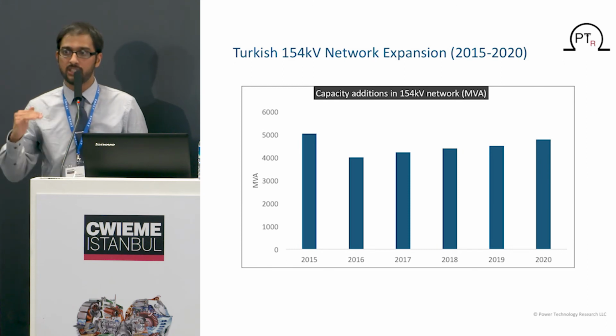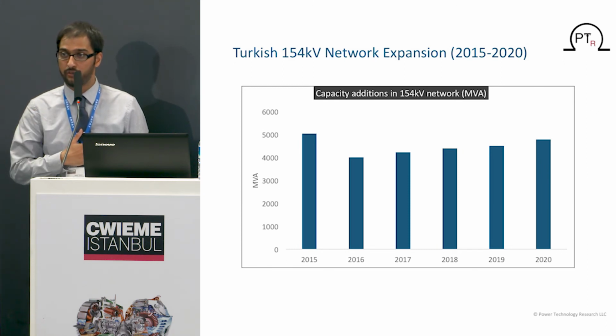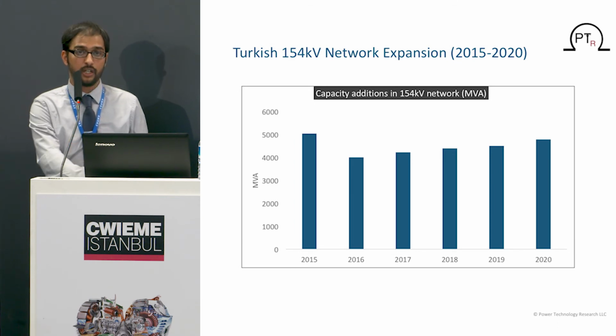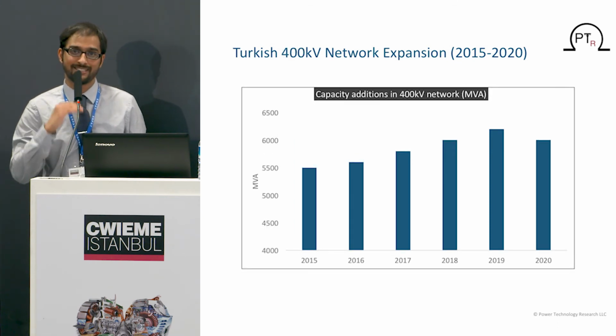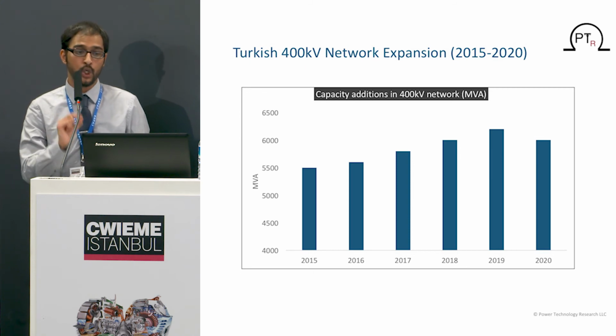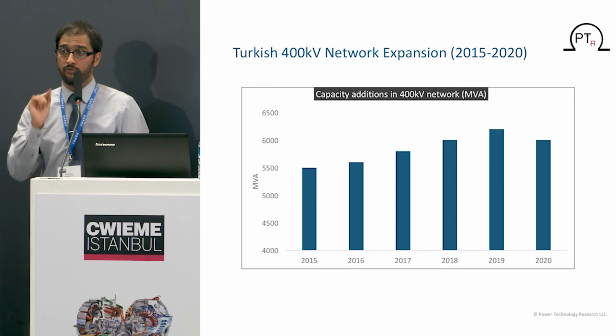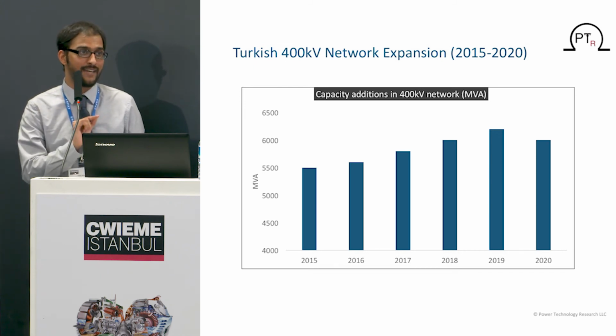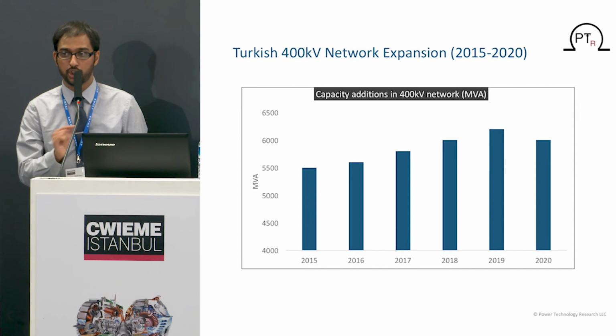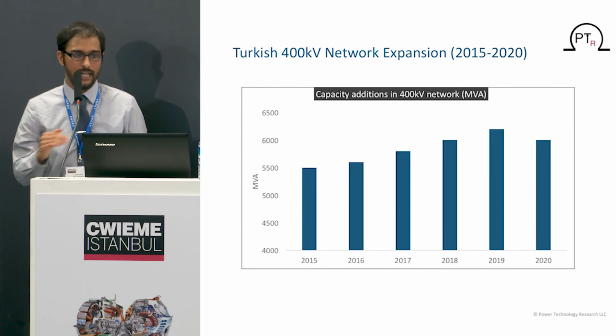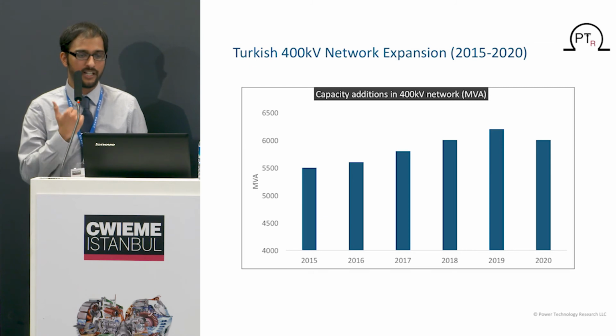We expect continuous increase of 154 kV MVA within Turkey's grid. And as we saw, the 400 kV did not have a lot of consistency, but in order to cope with this generation going into the network, we expect more 400 kV MVA transformers and more substations to be added, a consistent increase, almost touching 6,000 MVA per year, compared to the very inconsistent increase in MVA capacity we saw over the past years.